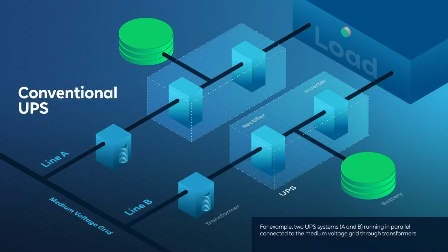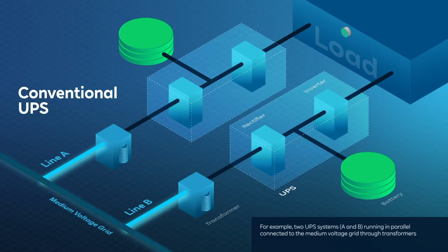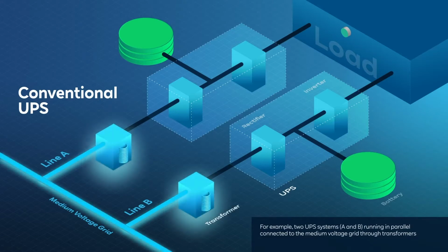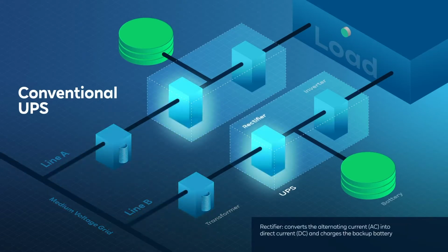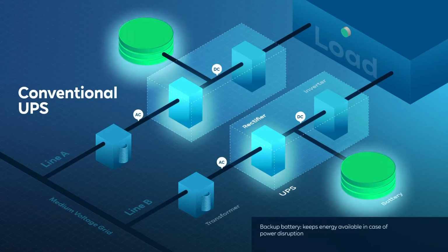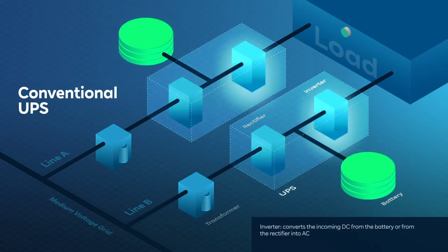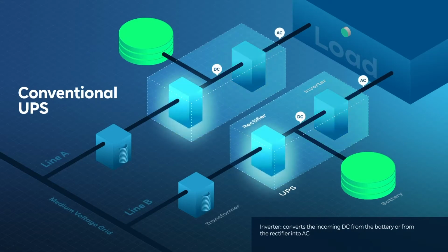For example, two UPS systems, A and B, running in parallel are connected to the medium voltage grid through a transformer. The UPS contains a rectifier that converts the incoming alternating current, AC, to direct current, DC, and also charges the backup battery. The inverter converts the incoming DC from the battery or from the rectifier to alternating current.